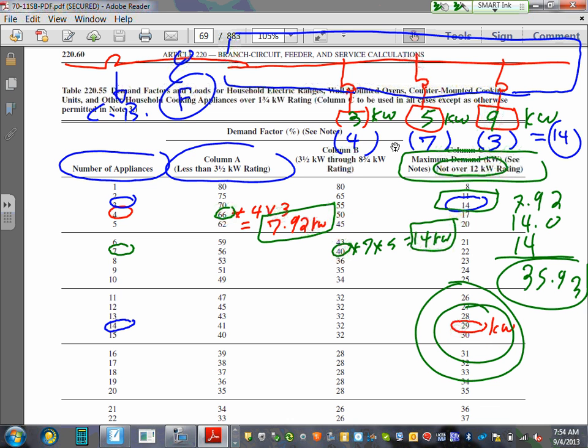Let me repeat myself. You look at all your ranges and ovens and counter-mounted cooking units. Look at all of them. If they're all 12 or less, apply C from the get-go. Right? Very easy. I have 14 of them, all under C, give me 29. Done. Step 1. Step 2. You're going to go check if any of these ranges are under A or B. Right? So, are they under A? Yep, they're all under A. So here's the under A. Apply A to only the ones under A. Right, man? Can you see that we applied A to only the 4, these guys? Because I did not apply them to the 5, because 5 is not under A.